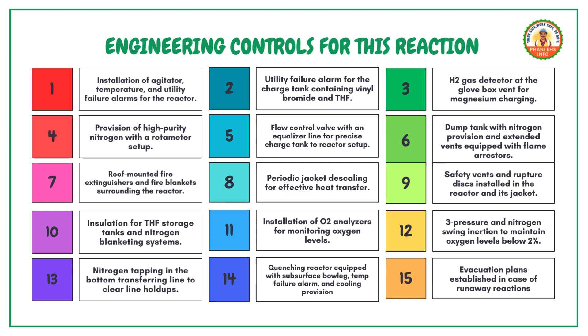Use 3-pressure and nitrogen swing inerting to maintain oxygen levels below 2%. Tap nitrogen in the bottom transferring line to clear line holdups. Equip the quenching reactor with a subsurface sparger, temperature failure alarm and cooling provision. Establish evacuation plans in case of runaway reactions.